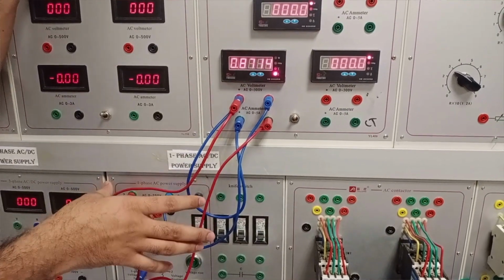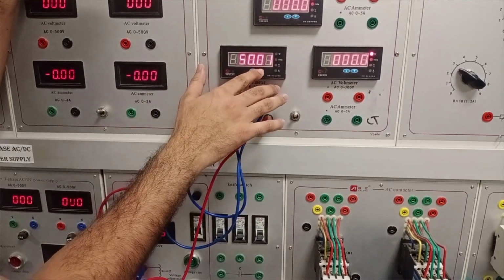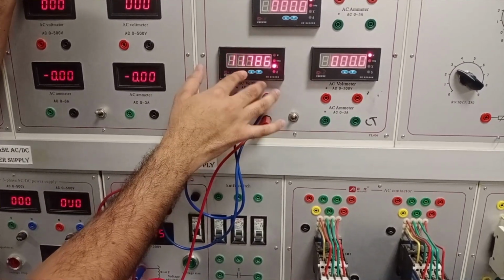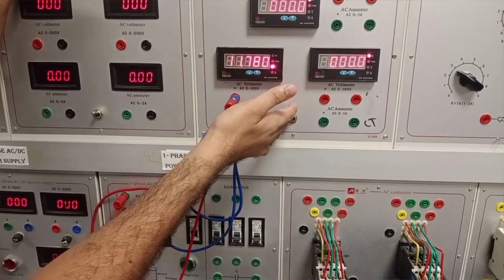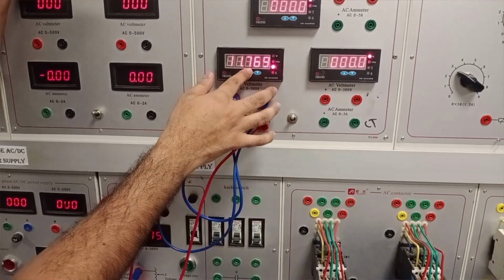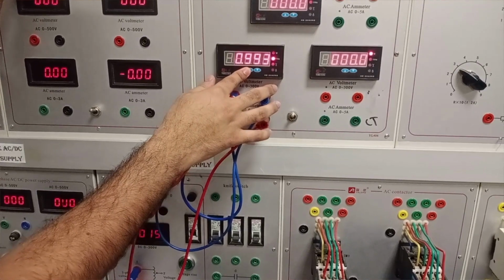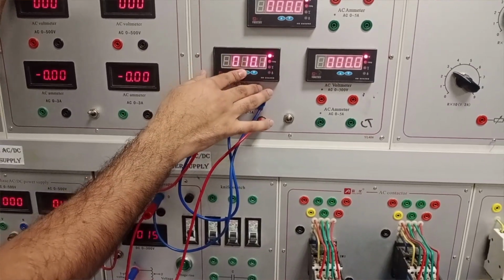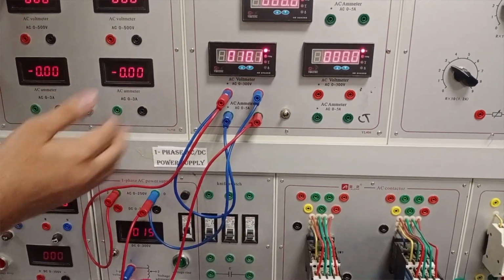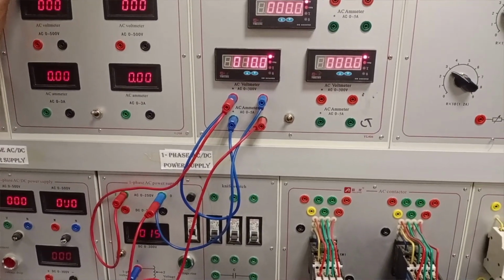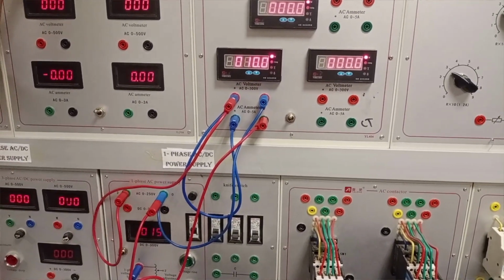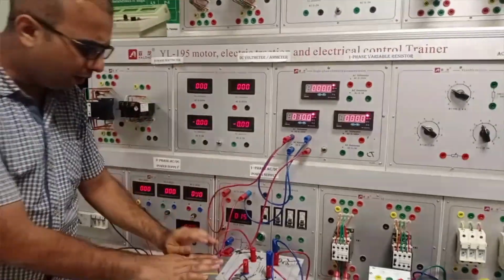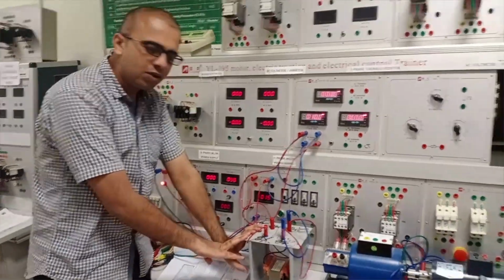windings of the transformer. This is the voltage, 11.7, and then this is the power factor of the transformer, 0.993, and the power is 10.1 watt, which is to be drawn from the primary side of the supply. So this was the experiment that we have done on this trainer. That was the short circuit test.